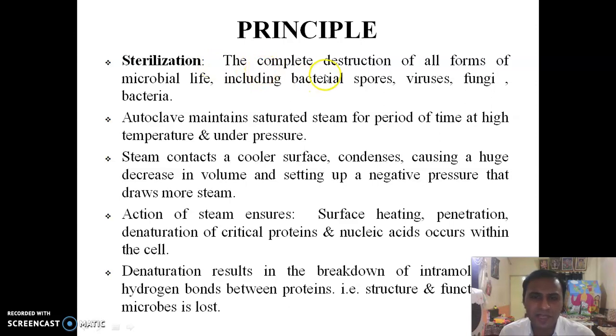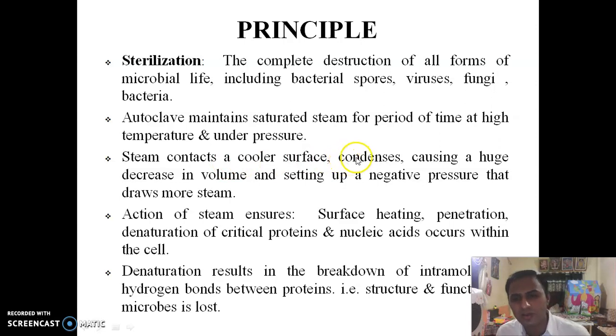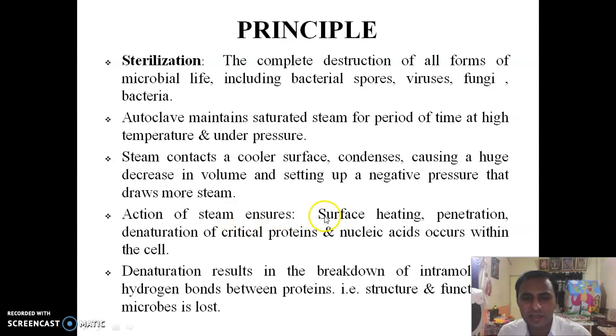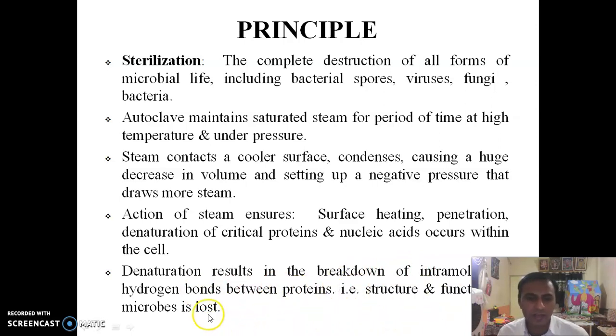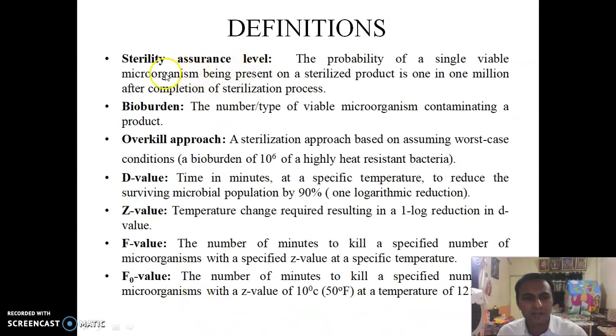Sterilization means the complete destruction of all forms of microbial life, including bacterial spores, viruses, fungi, and bacteria. The autoclave maintains saturated steam for a period of time at high temperature and under pressure. Steam contacting a cooler surface condenses, causing a huge decrease in volume and setting up a negative pressure that draws more steam. The action of steam on proteins ensures surface heating, penetration, and denaturation of critical proteins and nucleic acids, resulting in the breakdown of intramolecular hydrogen bonds between proteins, so the structure and function of microbes is lost.